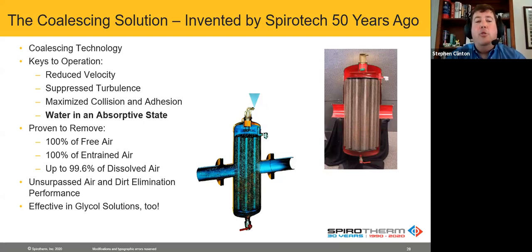What we're different is that we're not spinning. We're not trying to use centrifugal force. We're doing the opposite. We want the water to come in. As you saw in that introductory video, I want to include that one. So there are certain things you were able to see graphically that typically, if you were in a presentation in person, you would see at the demo unit that we have. If you've ever been by our booth at CX Energy or other conferences, we have a demo unit that you can see air and dirt being removed. But basically, we're able to remove air and also dirt by slowing the velocity of the fluid, suppressing the turbulence, and we want the opportunity for those air bubbles to come in, slow down, and the big ones to rise to the top.